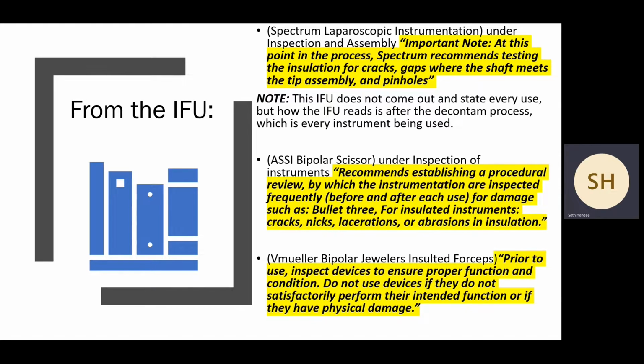So ASSI, for their bipolar forceps, recommends establishing a procedural review by which the instruments are inspected frequently before and after use for damage such as bullet 3, and bullet 3 is for insulated instruments. That's cracks, nicks, lacerations, or abrasions. Another one, because many of us have the V. Mueller bipolar forceps. Prior to use, inspect the device to ensure proper function and condition. Do not use any device if they do not satisfactorily perform their intended function, or if they have physical damage. So there you are again. V. Mueller's going back to the performance of this device, and the performance of the coating is to contain that electrosurgical energy.